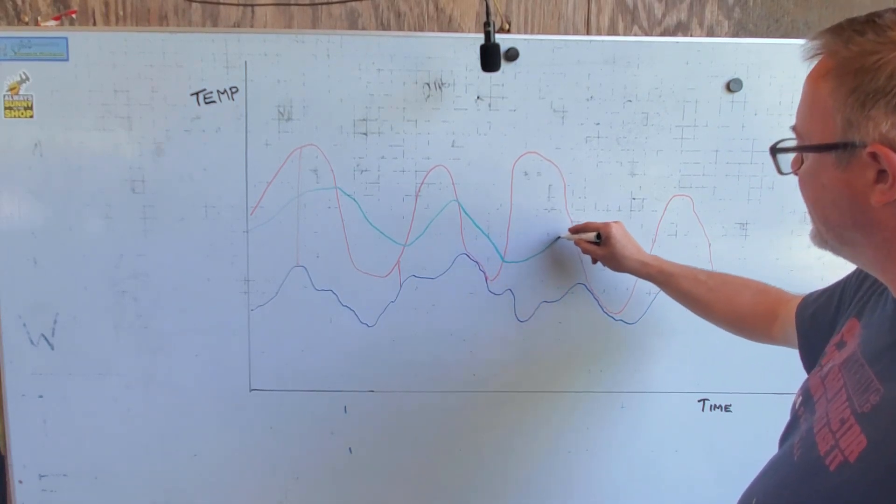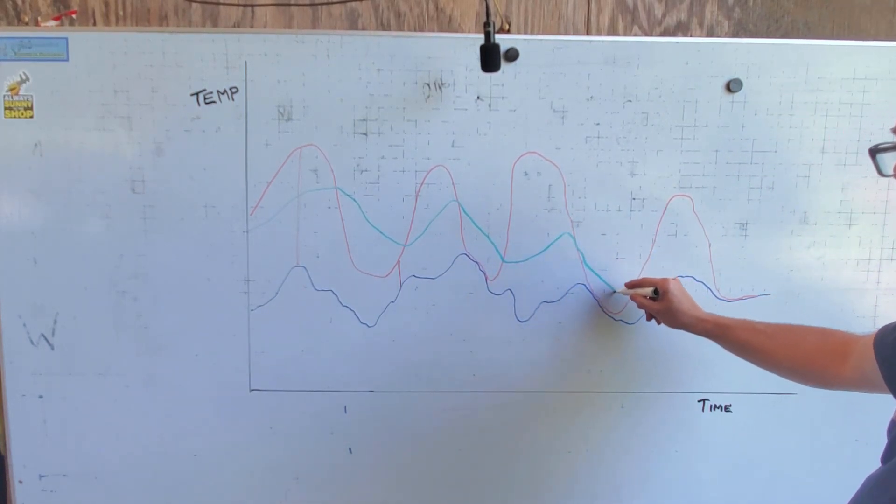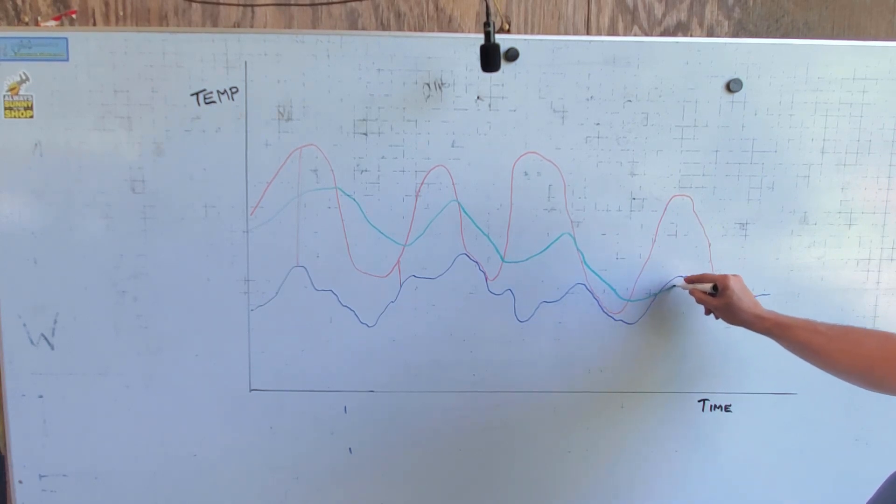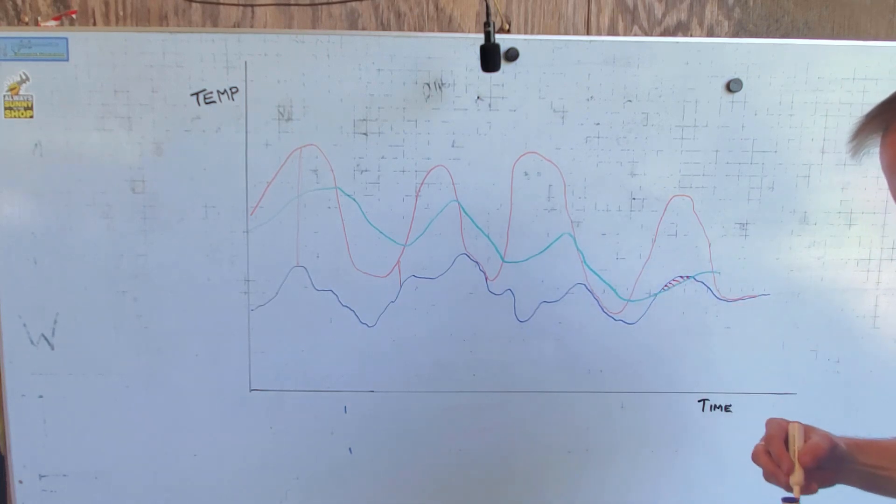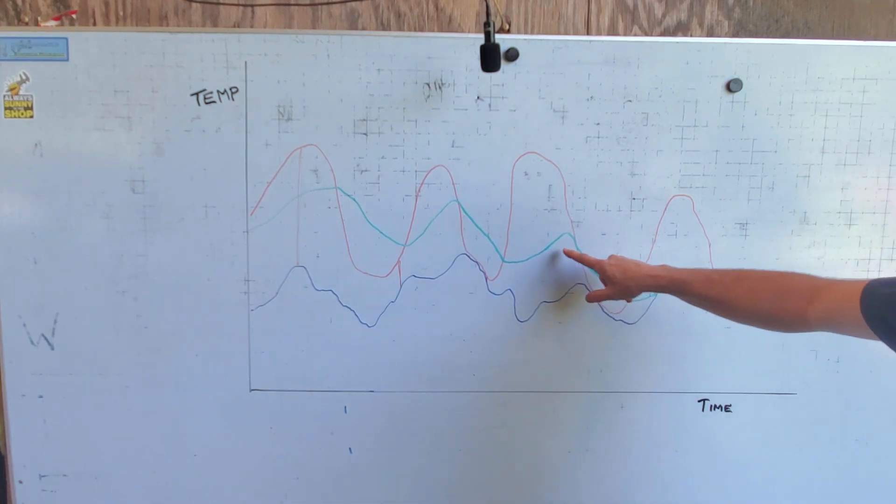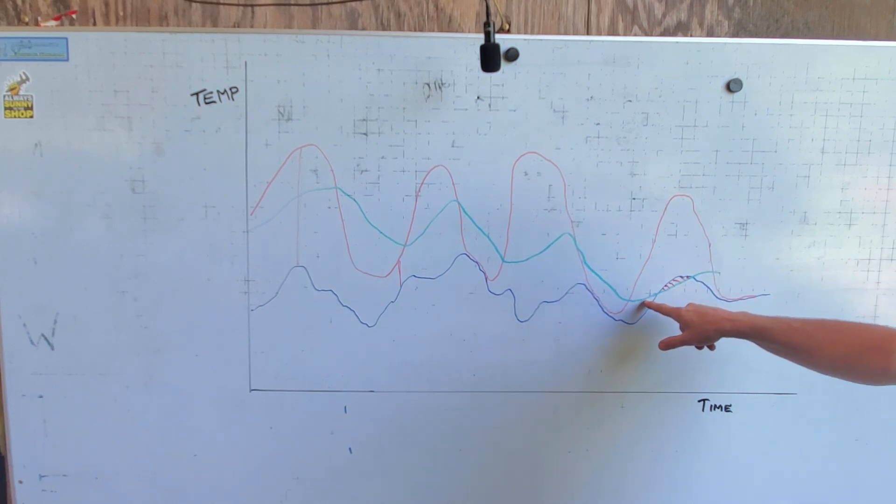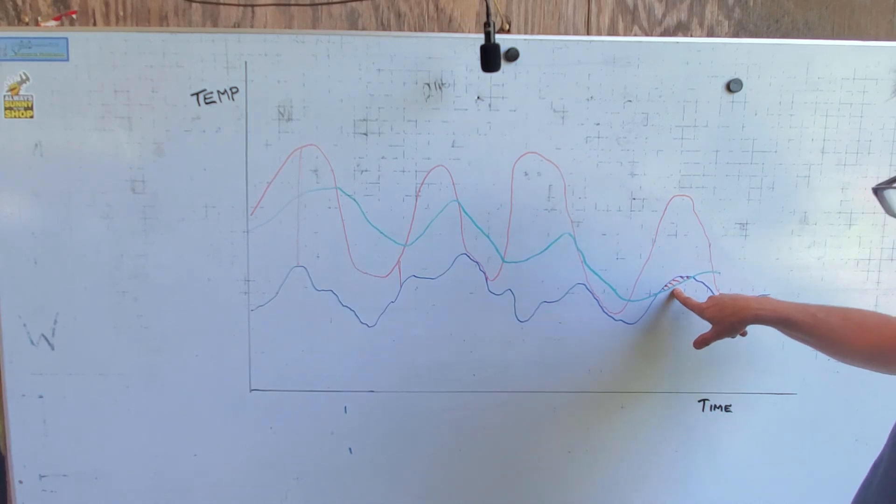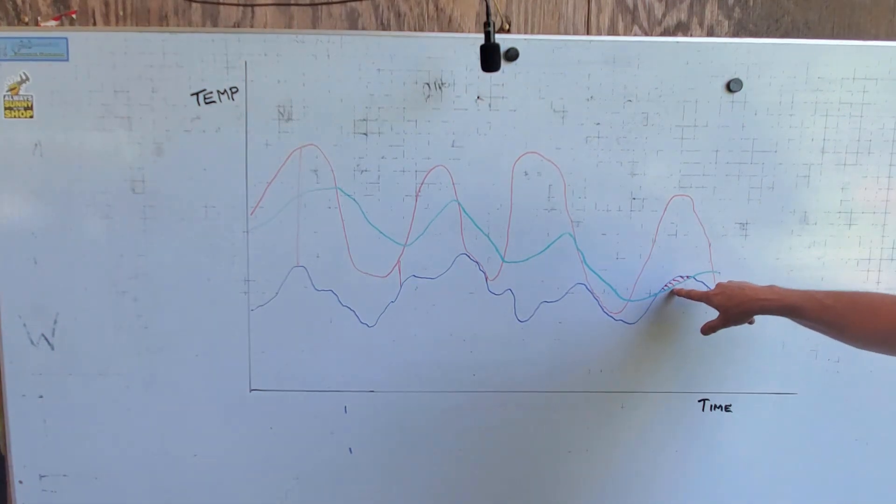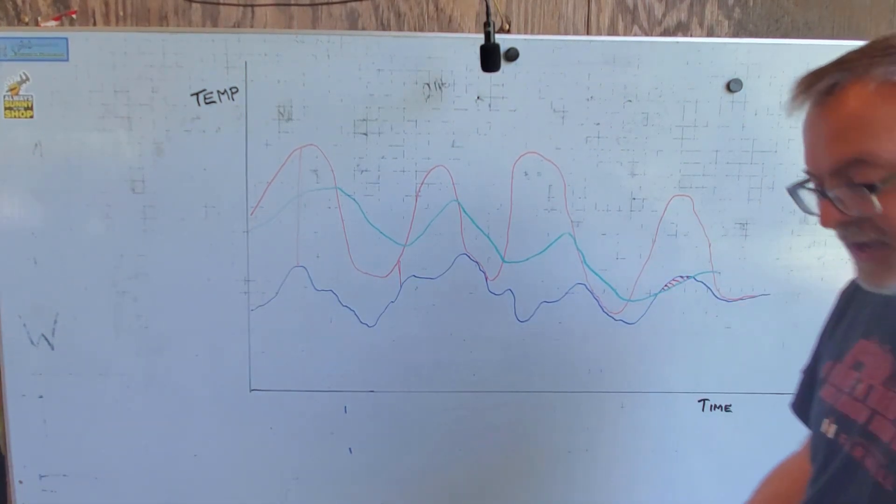Where did we get into trouble? We got into trouble right in this little zone here. And the reason we got into trouble is because the surface, the temperature of the cast iron surface all of a sudden was lower than the dew point temperature. And so this cast iron surface is now the ice-cold glass of water, and water from the air is going to condense on the surface of the machine. How do you fix this?